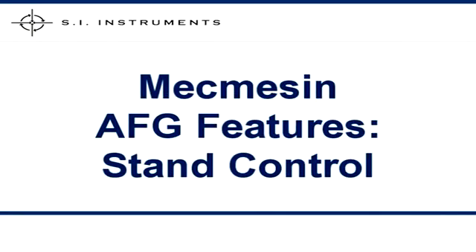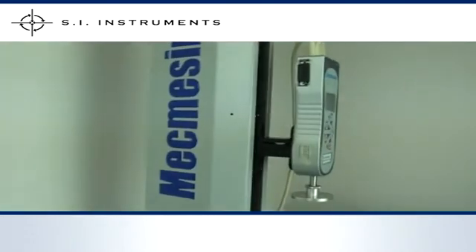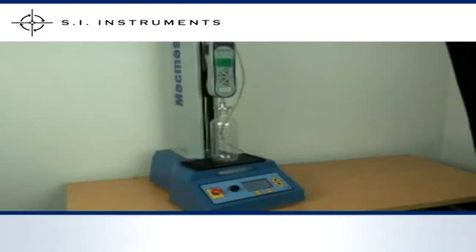When the Mecmesin Advanced Force Gauge is used in conjunction with the Mecmesin Multi-Test D test stand, the gauge can travel between the limit switches. However, it is also possible for the Advanced Force Gauge to signal the stand when the test has been completed. This feature is a perfect time-saving operation. The feedback can be either by detecting a break or collapse point, or at a pre-programmed force.